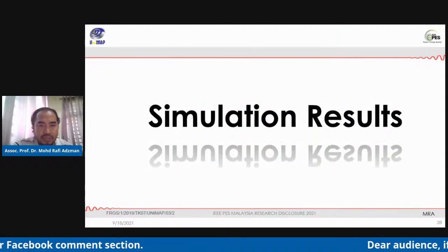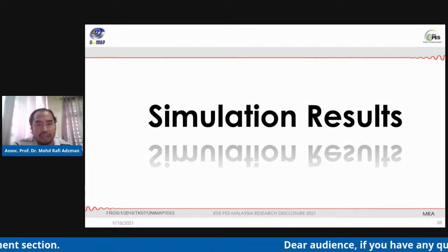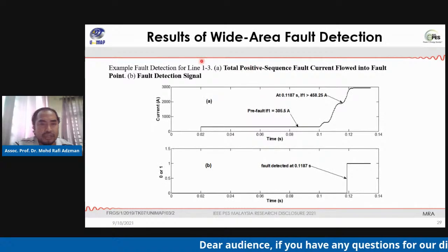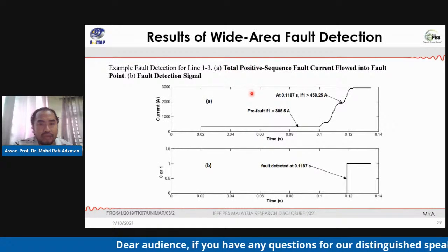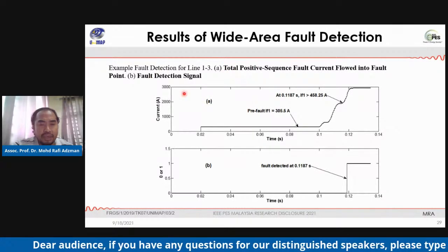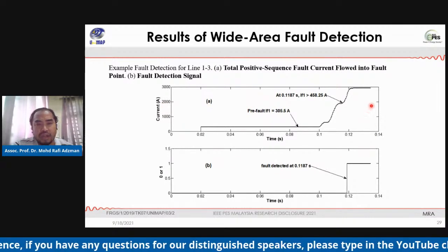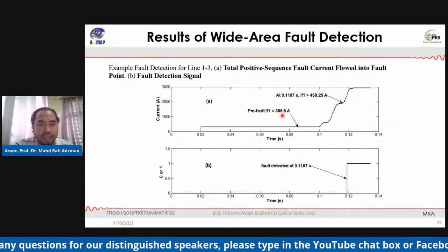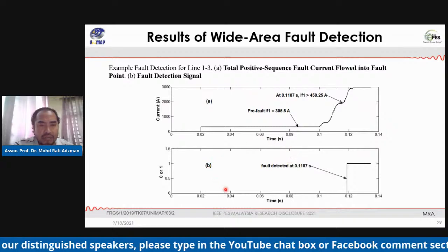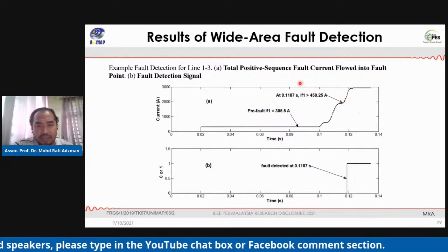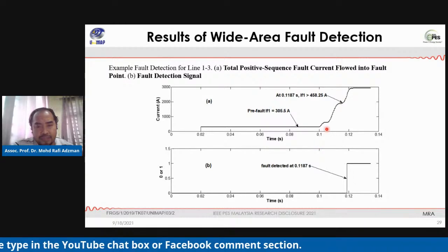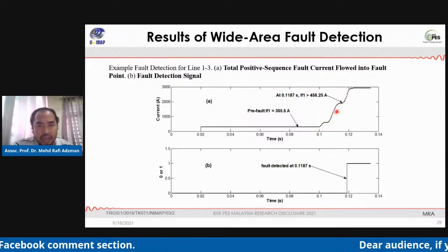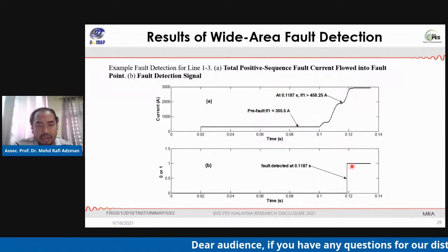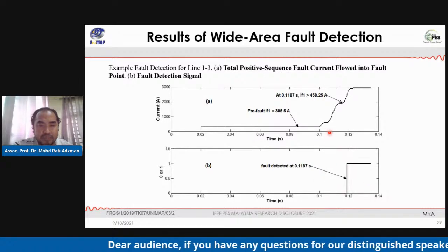Okay, let's see the simulation results. First, the results based on the wide area fault detection. Here is an example: (A) the positive sequence fault current flowing into the fault point, and (B) the fault detection signal. From this figure, we can see that the fault started at 0.1, and at time 0.1187, the fault has been detected.